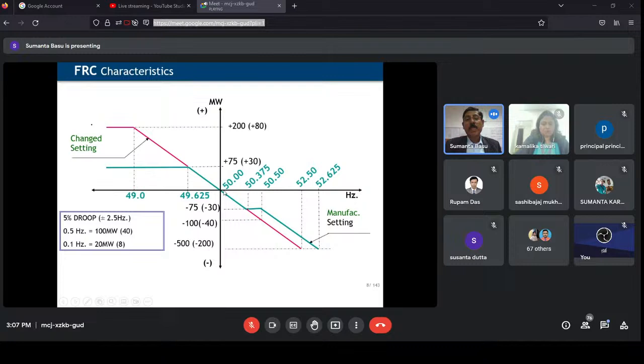So you see that it passes through the 0, 0 line. That means that no ripple in the power system frequency has been considered here. If there are any small variations in the frequency, there will always be oscillations in the power generating stations. Mainly if it is a steam turbine driven generator, there will always be variations of the governors there. If it is a renewable energy driven converter, the frequency control techniques also have to be implemented to handle these small frequency variations. So this is called the ripple effect.